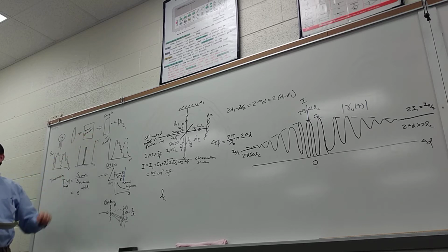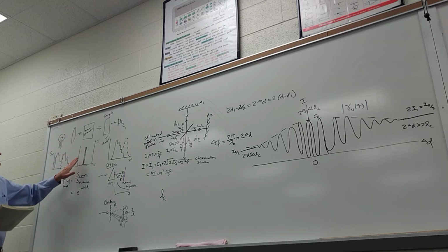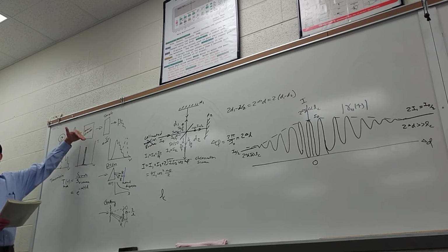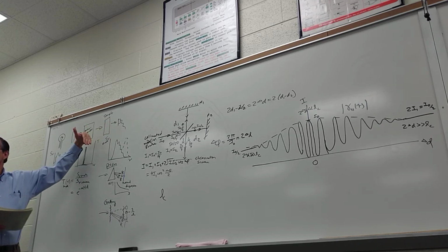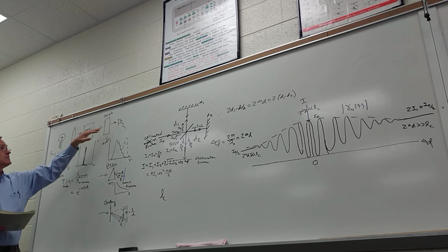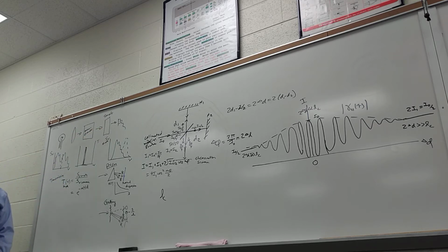Is rotating the prism or the grating out of the question? No, that's legal. You can do it. Wait, so why would we care if it went straight through? It's just more convenient instrument-wise. If you change this wavelength and it comes out at a different angle, then all this stuff needs to come out at that different angle, or you're going to be sampling through a different region of your sample and introducing all kinds of errors. But that's a topic for another day.